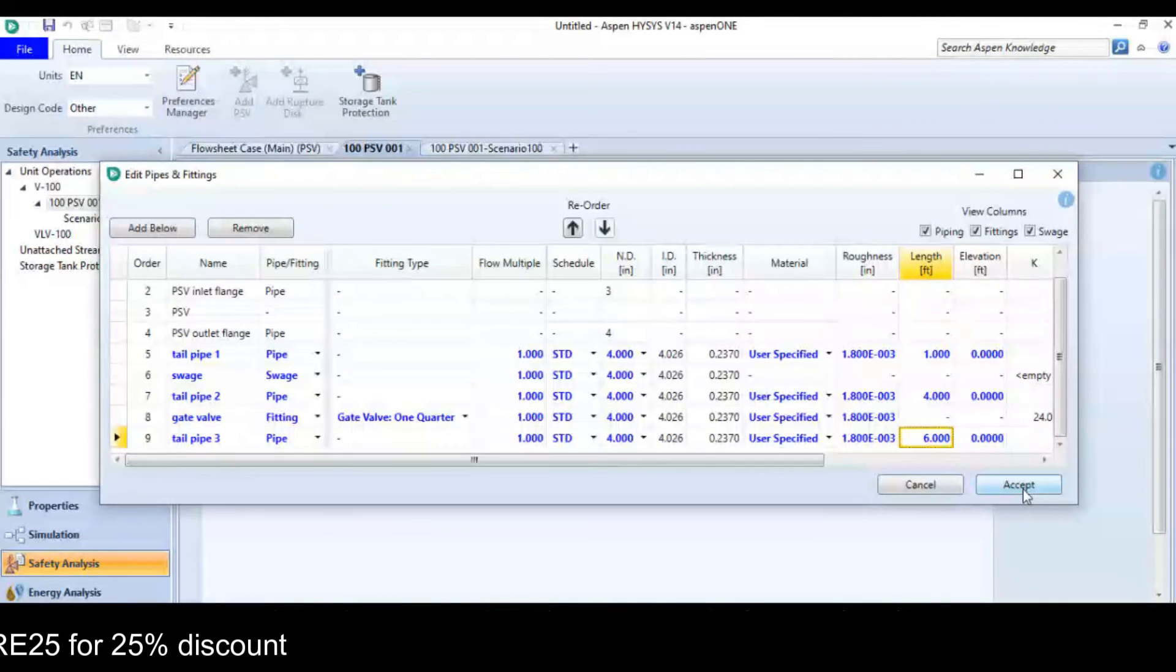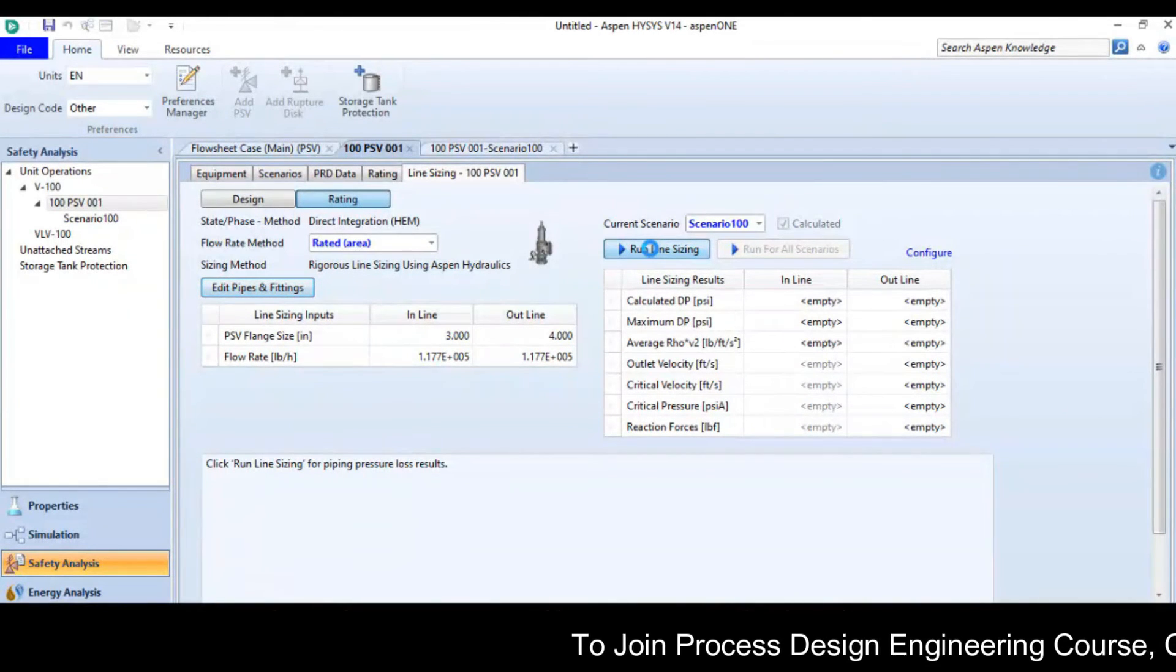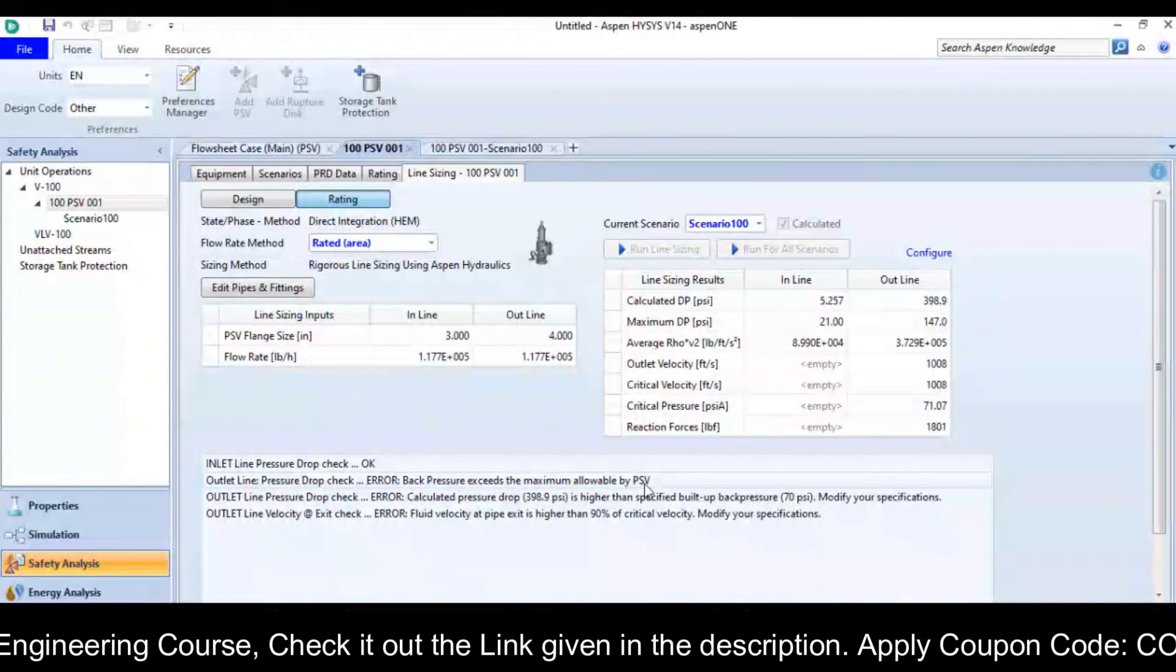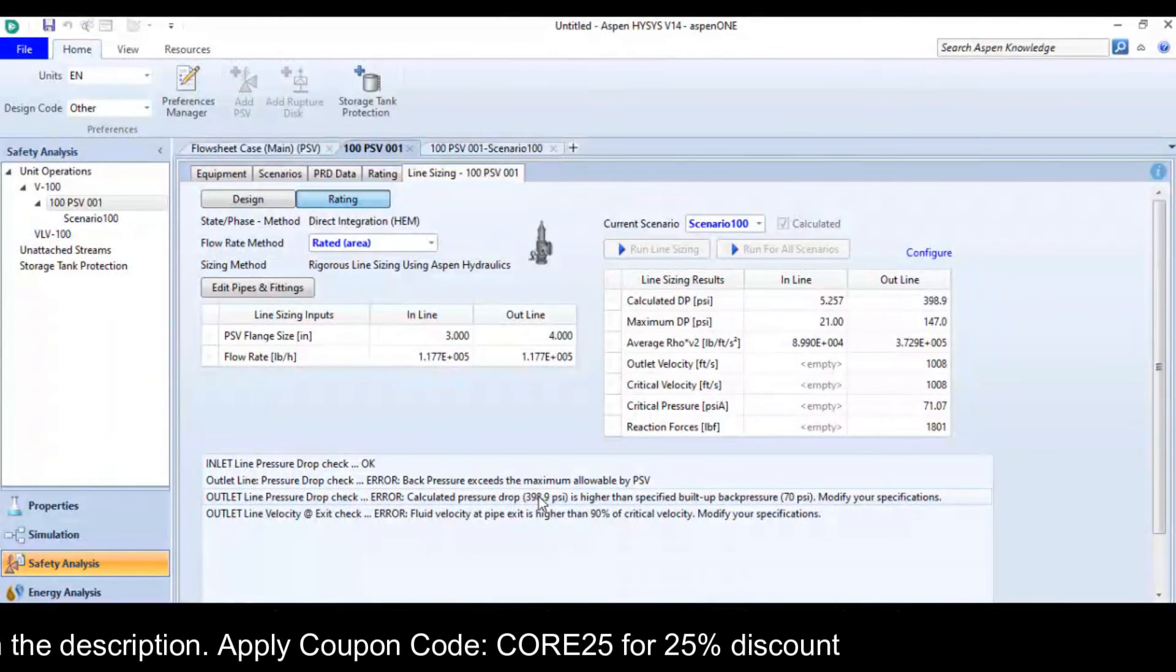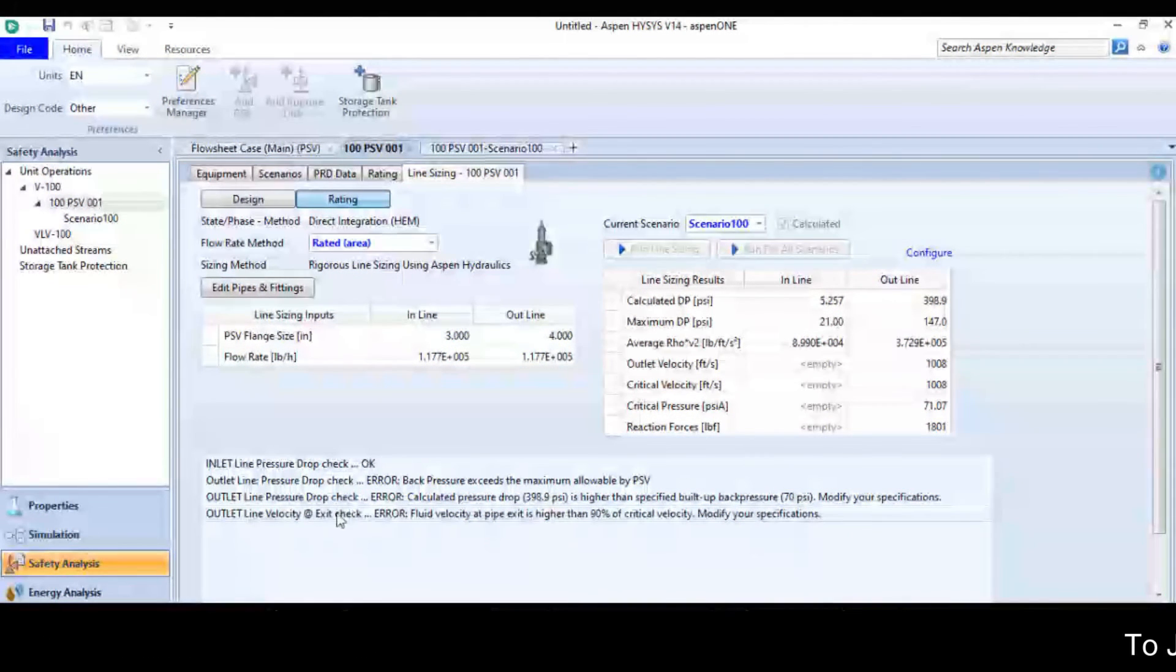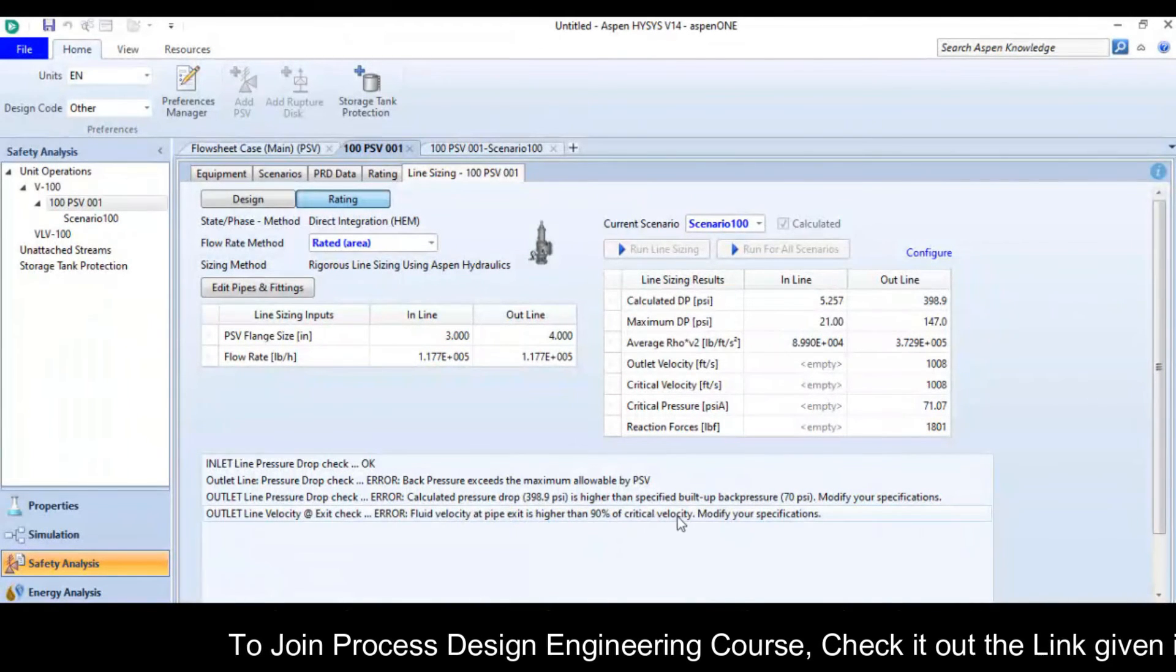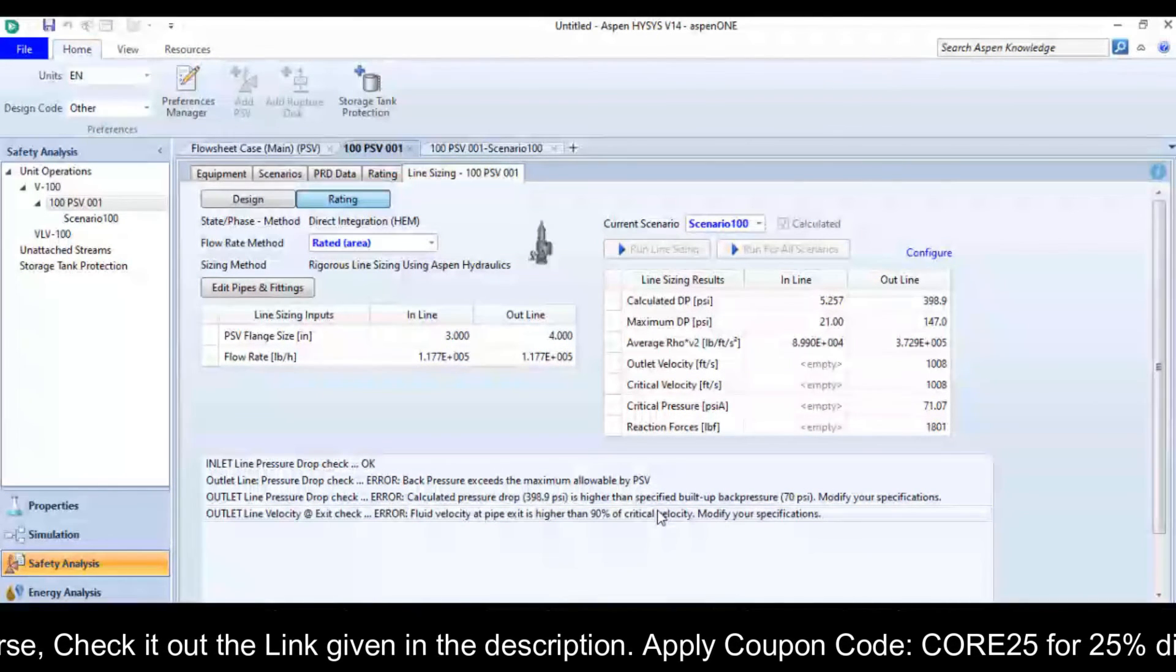Now I will click on accept button and click run line sizing option. The outlet line pressure drop check error, back pressure exceeds the maximum allowable by the PSV. Outlet line pressure drop check error, calculated pressure drop is higher than the specified build up back pressure 70 psi and also error regarding exit velocity. Fluid velocity at the pipe exit is higher than 90% of the critical velocity. So it means we need to make some changes there.